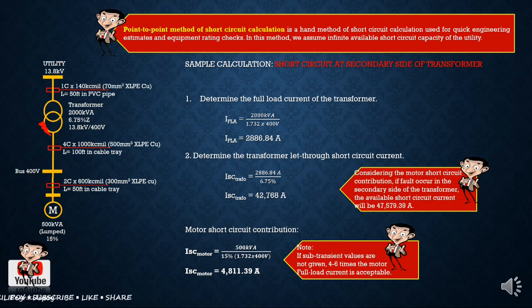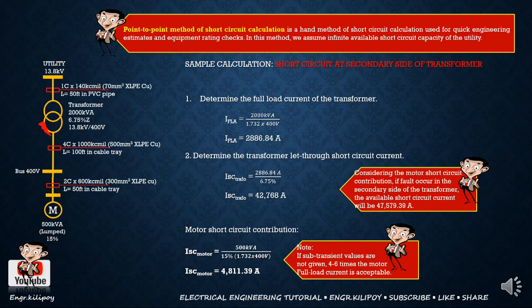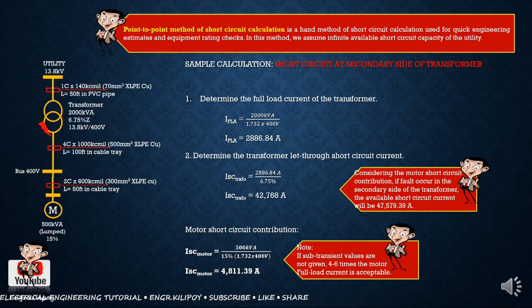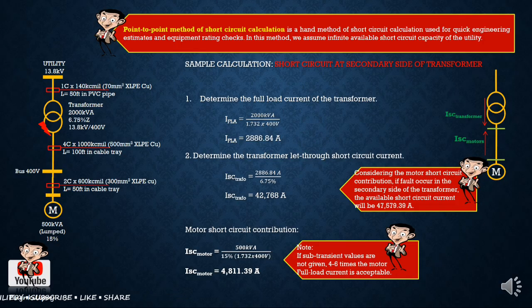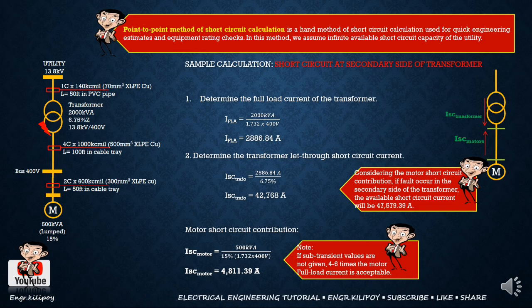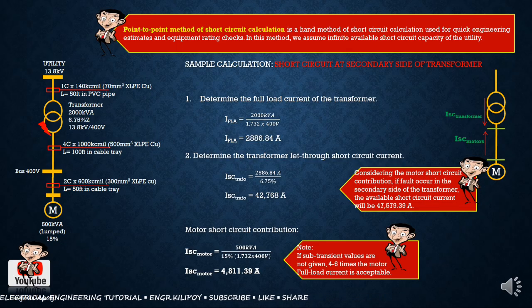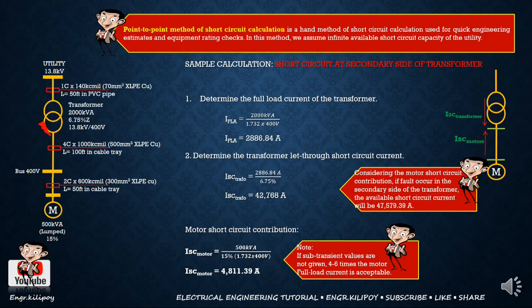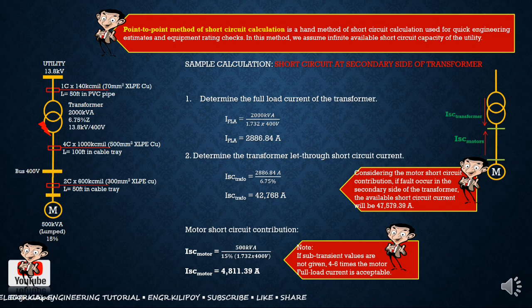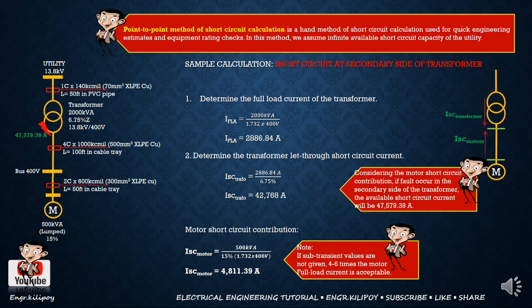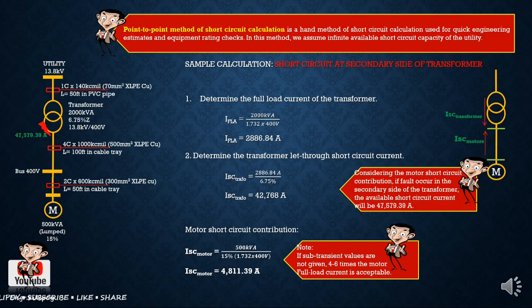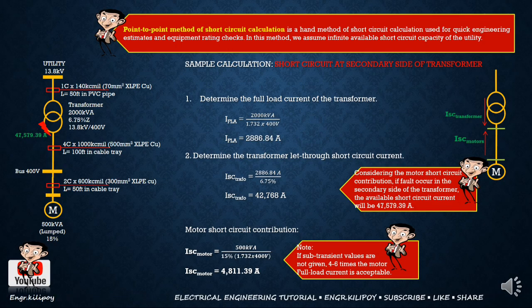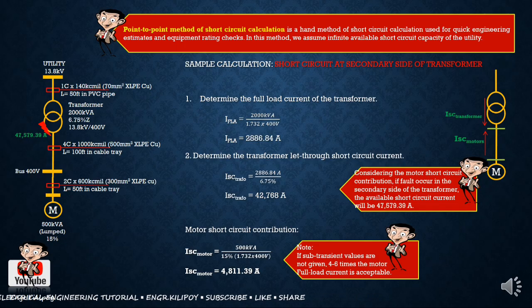So in this case, meron kang electro short circuit current sa transformer secondary side at pagkakaroon ka ng short circuit contribution galing sa motor. So from this point, magkakaroon ka ng 42,768 ampere plus yung iyong short circuit contribution ng motor na 4,811. So sa makatuwid, meron kang 47,579.39 ampere or 48 kilo ampere doon sa secondary side ng transformer kapag nagkaroon ng 3-phase short circuit doon sa secondary side ng iyong transformer.